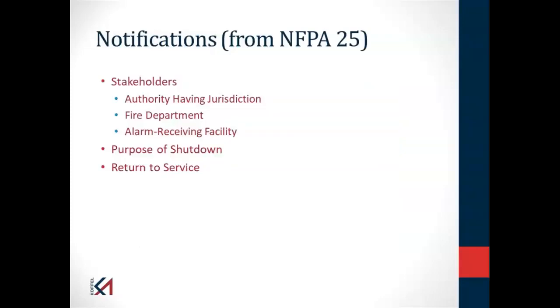There are certain notifications before you do inspection, test, and maintenance. The last thing you want is for the fire department to respond because you're testing the fire alarm or sprinkler system. But at the same time, we don't want to create a false sense of security. I've been in buildings where they're testing the fire alarm system and don't put out any pre-notification, and the people just ignore the system because it keeps going off.